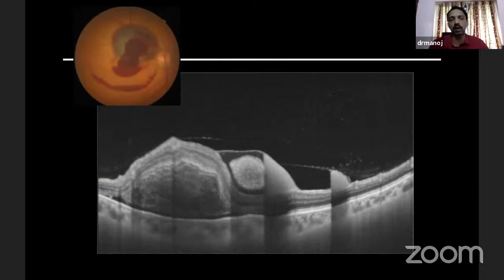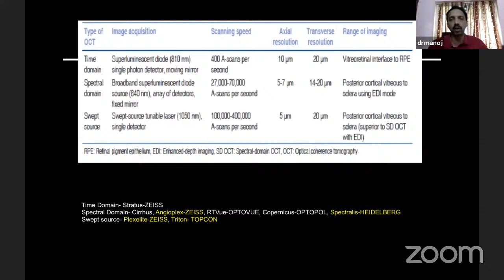So basically, you need to understand that there are three kinds of machines. You have the time domain machines, the spectral domain machines, and swept source OCT machines. The time domain machines are the earlier generation machines. The resolution of these machines is poor. The study of the vitreoretinal interface is very poor in these machines. Study of the outer retina or the photoreceptors also is poor in this machine. So that has to be kept in mind. The spectral domain machines have good resolution, and that is what we commonly use. We also have the swept source OCT machine, which has the highest resolution. And this is the machine that one needs to use if you have to study choroidal pathology in detail.